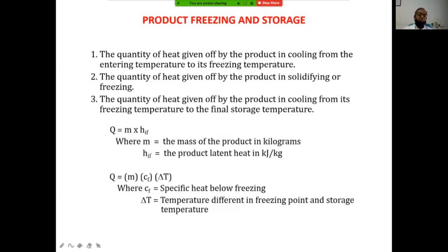the specific heat above freezing, and then the product latent heat load. How much portion of the water in the ice cream is frozen is to be measured, and accordingly that load comes here. So there are three loads: one is product cooling from the entering temperature to freezing temperature, then the product solidifying load, that is freezing, and third is the product cooling after freezing load, that is this load. Now see this chart.